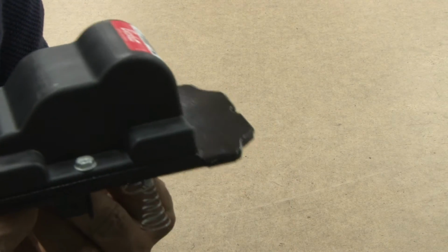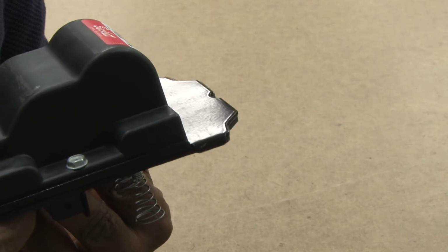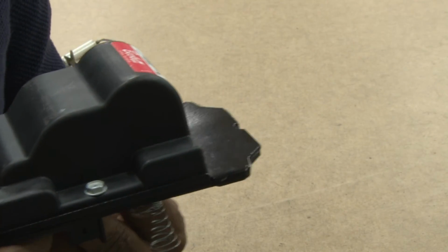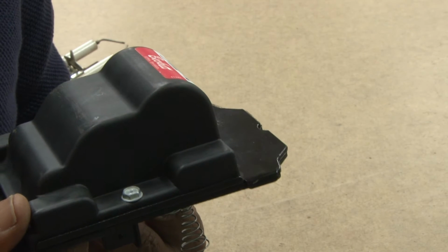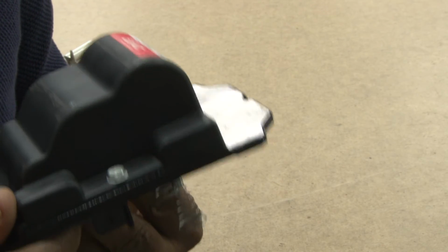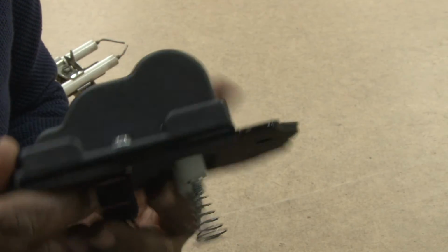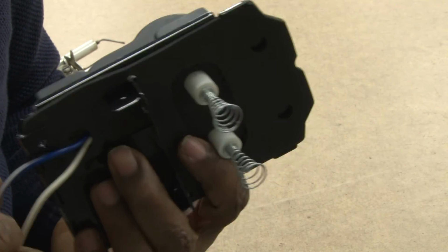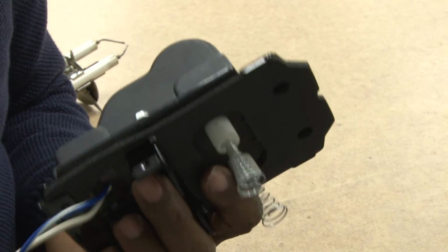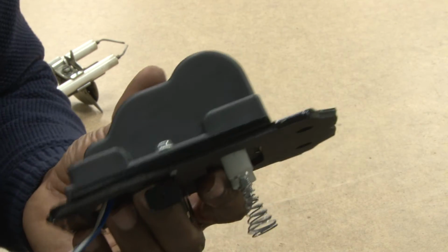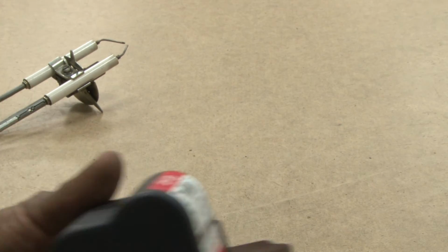This is a newer type. It's designed as a spark generator. It's a little bit more efficient than the older style they had years ago, which was a very large, heavy transformer. These days they produce a very good spark, but it takes fewer windings and less weight, so it's a lot more efficient.